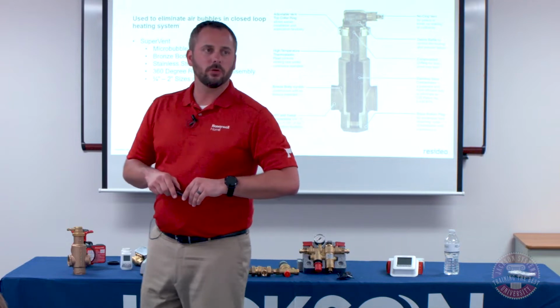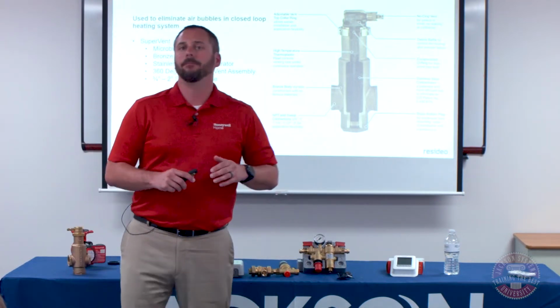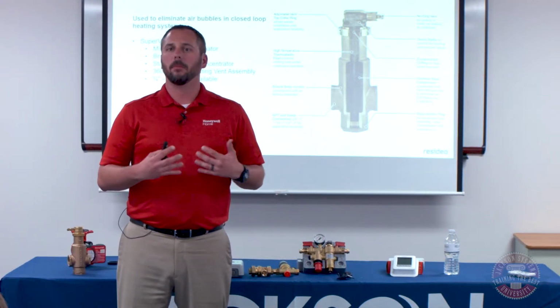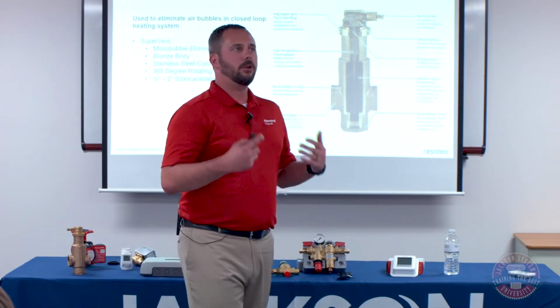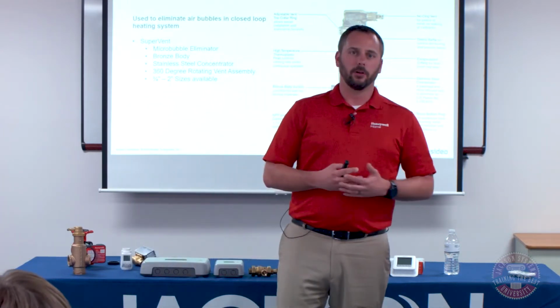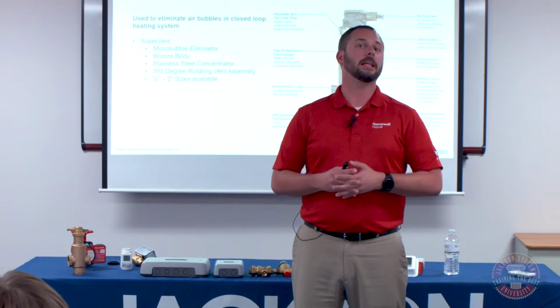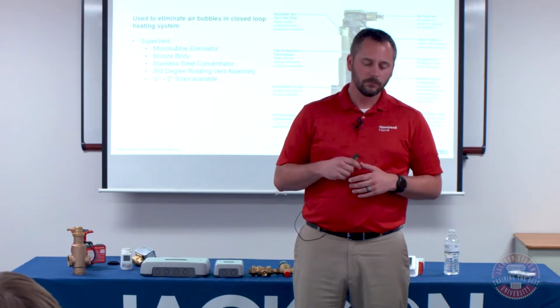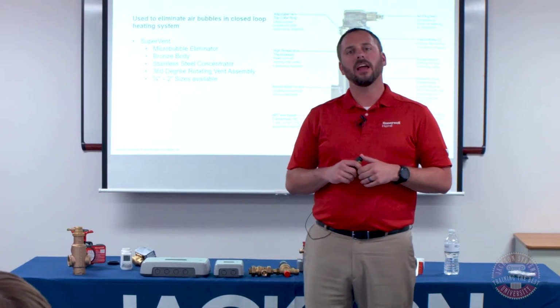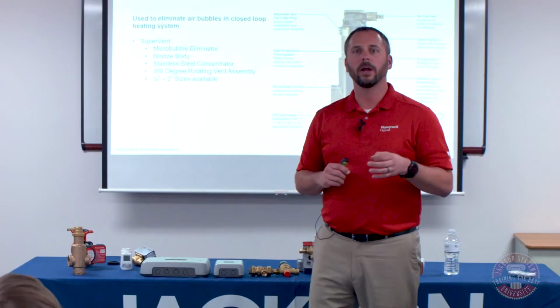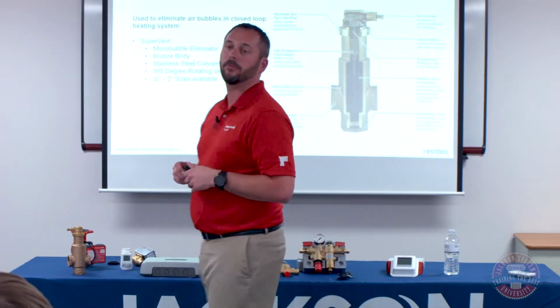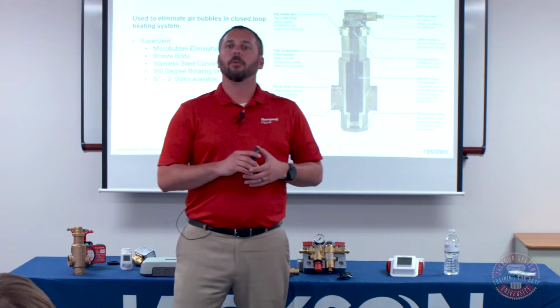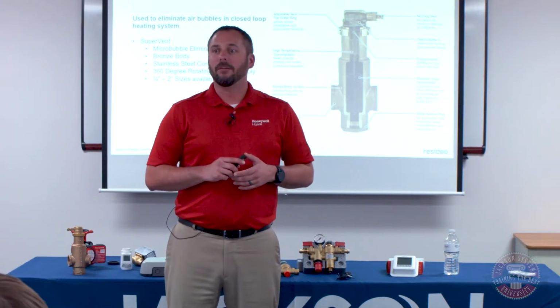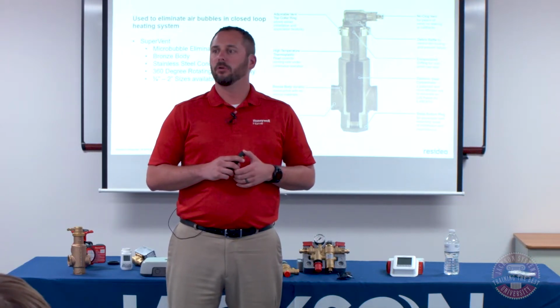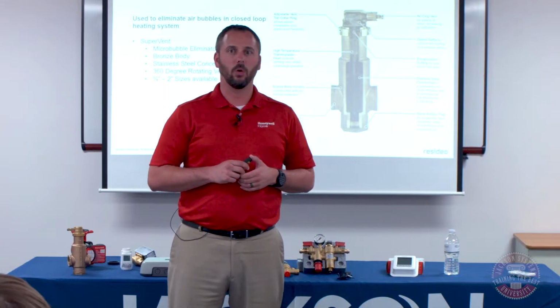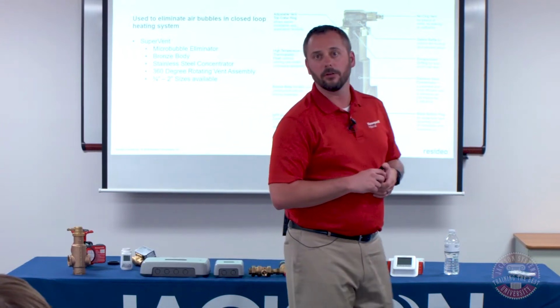What I'm showing you now is the super vent. So the super vent is the micro bubble air eliminator. If you have a modulating condensing boiler, and in my opinion really any boiler in today's world, the modulating and condensing boilers have very small waterways through the manifolds inside the heat exchanger. So if you end up with air bubbles inside of there, you can end up with cavitation, because that boiler is producing so much heat that it's actually boiling the water because you've got air that's slowing it down.